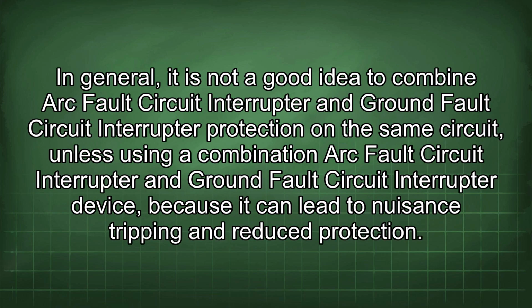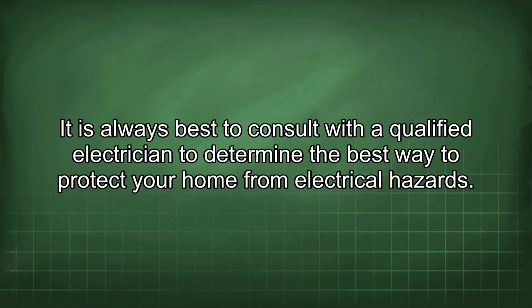In general, it is not a good idea to combine arc fault circuit interrupter and ground fault circuit interrupter protection on the same circuit unless using a combination arc fault circuit interrupter and ground fault circuit interrupter device, because it can lead to nuisance tripping and reduced protection. It is always best to consult with a qualified electrician to determine the best way to protect your home from electrical hazard.